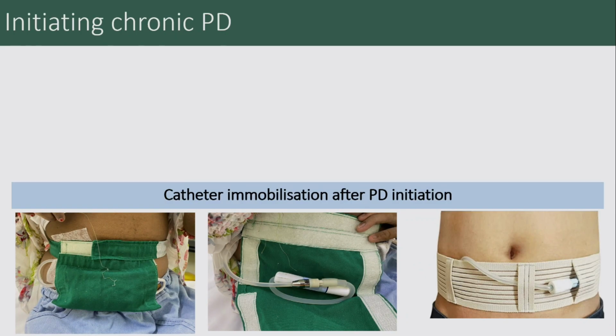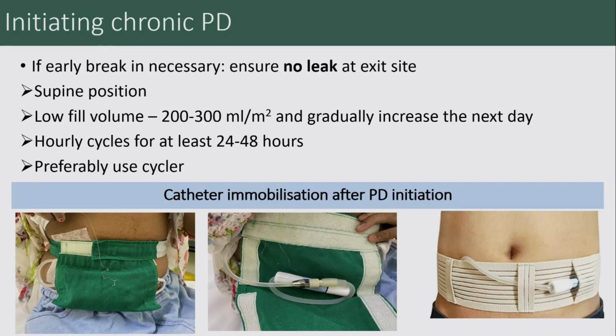Now, initiating chronic PD: if early break-in is required for conditions where you cannot wait for dialysis, then ensure that there is no leak at the exit site. So ideally, to avoid this kind of situation, it's better that PD insertion is done as a planned procedure and not as an emergency. You can keep the child on hemodialysis, then insert the PD catheter and wait for the break-in period to limit these leaks. The PD should always be done in a supine position so as to recruit the maximum area of the peritoneal membrane. And you initially start with low fill volumes of about 200 to 300 mL per meter square and gradually increase as tolerated.